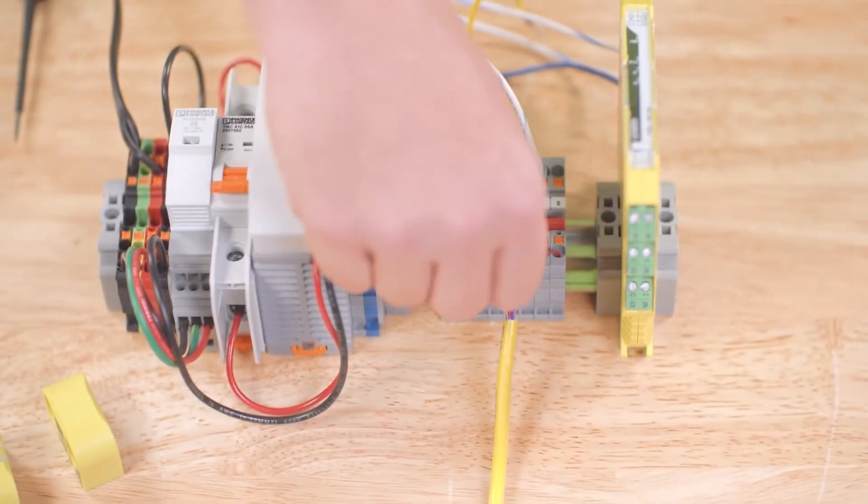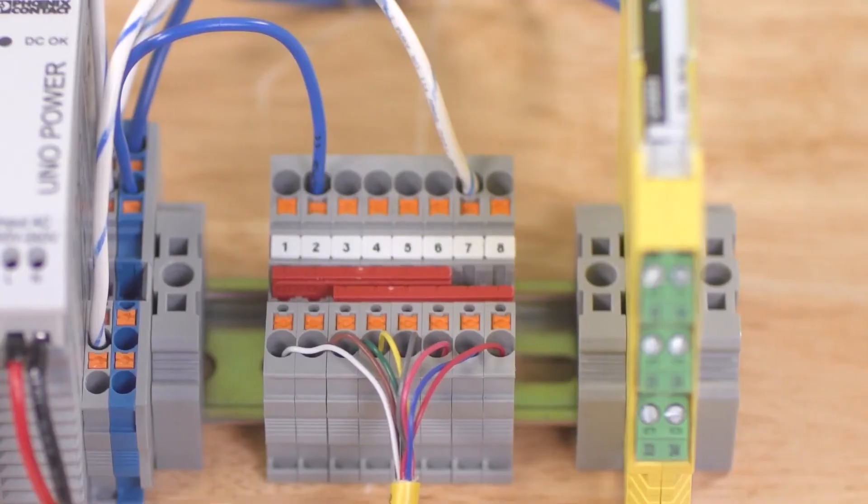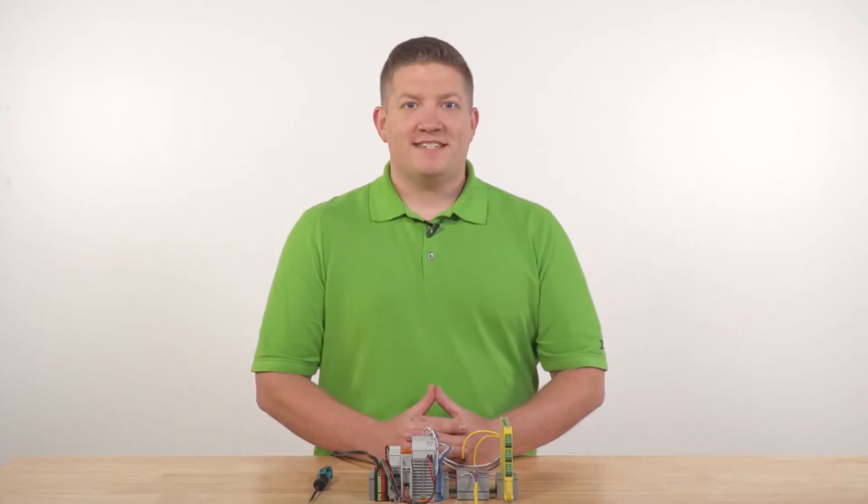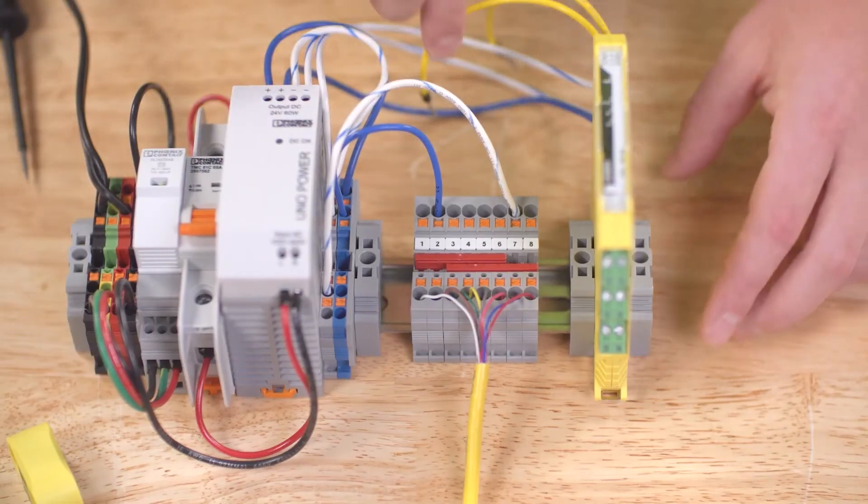Next, for the automatic start-up behavior, the sensor expects a clock signal from the F-O-1A safety output, so we'll jumper pin 8 to pin 3 using this bridge. If this connection is not present at power on, the sensor will expect a manual monitored reset into pin 8 instead.